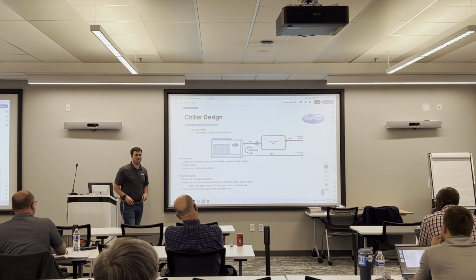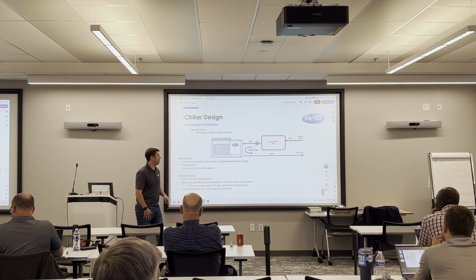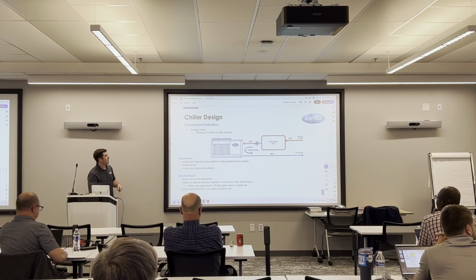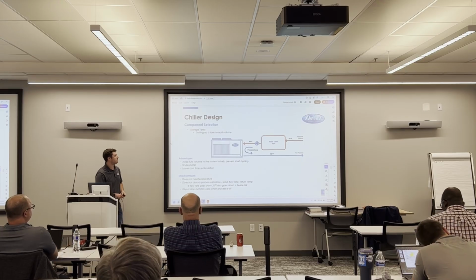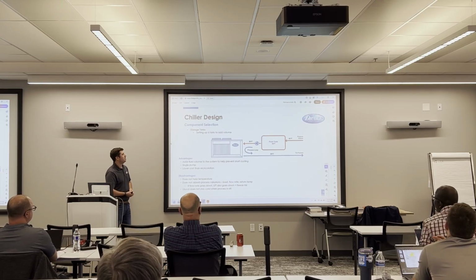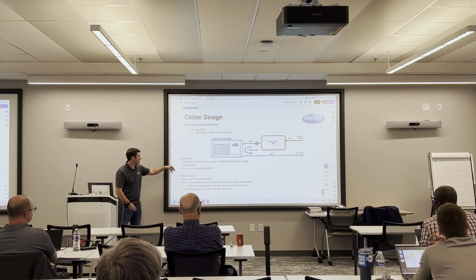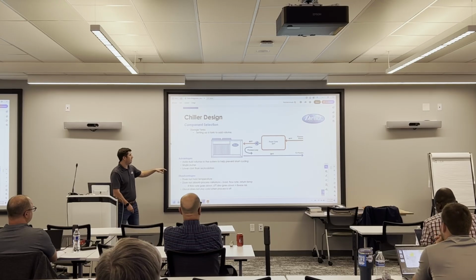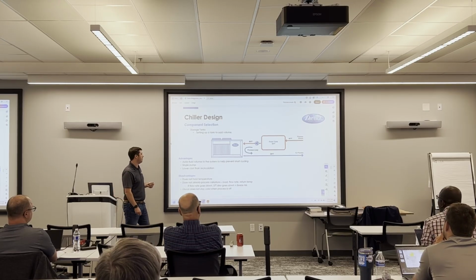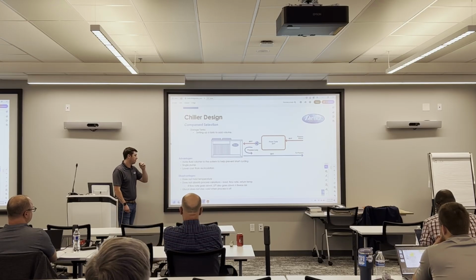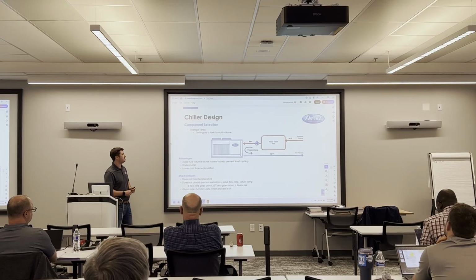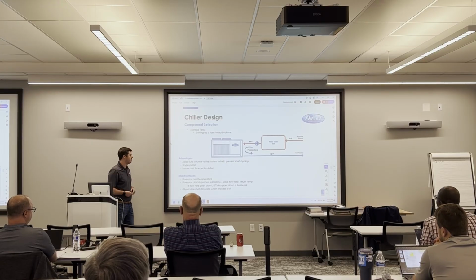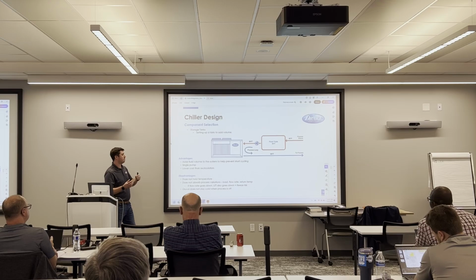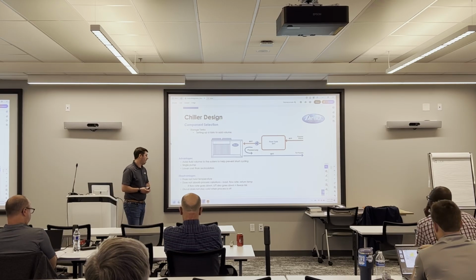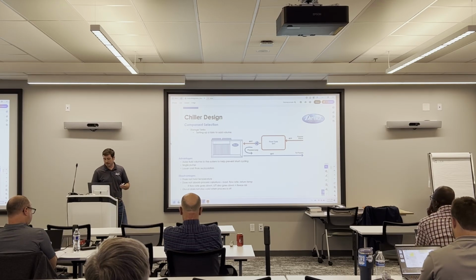We don't really need to get into industries today, so we'll just wrap up components and we'll get going. Last setup is a storage tank, essentially just adding volume to the chilled process loop. So obviously some advantages: you're going to add volume, and it's a single pump, so you can save on your costs there. You don't need to add that secondary pump. Some disadvantages: you're not holding temperature as well as you would with a recirculation system. It's not going to absorb those process variations. And the glycol doesn't stay cold when the process is off, so you're not going to have that on-demand cooling.